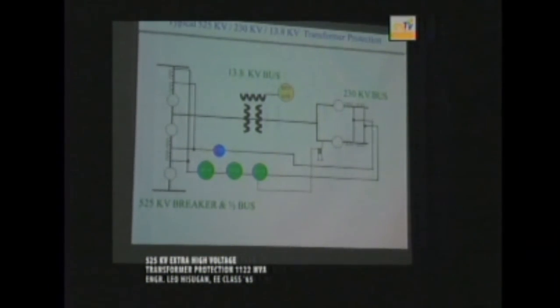On the low side of the bank, if this is the 230 kV bus here, we utilize 2 relays, set A and set B, for example, and they are fully redundant. So the low side of the bank utilizes phase distance protection towards the transformer, and also ground directional protection towards the transformer. All redundant, set A and set B.